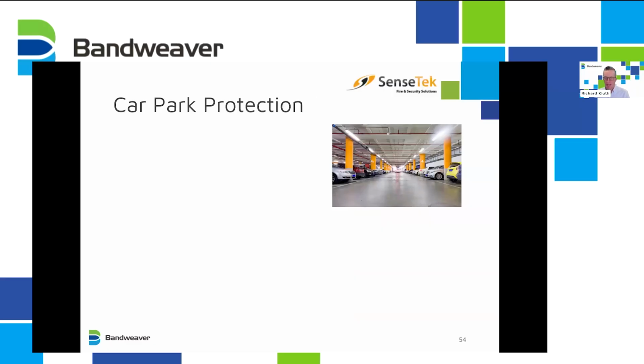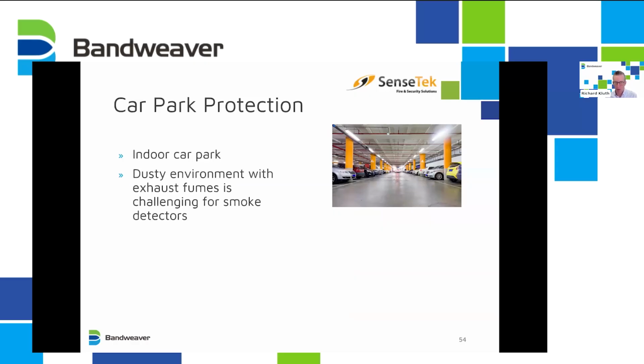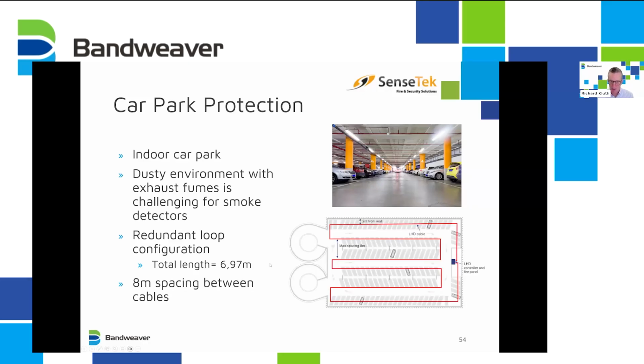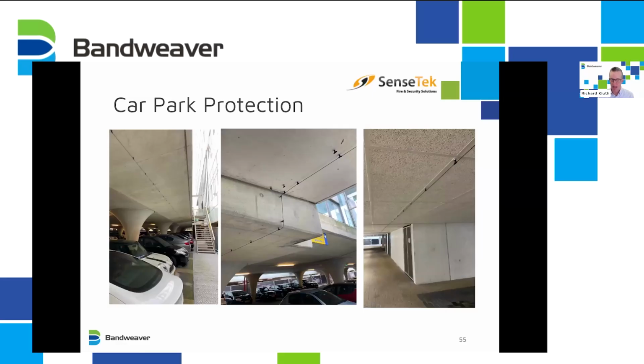So our final example is looking at car parks, and the reason for this is in the Netherlands they do car park commissioning tests that really demonstrate how sensitive this system can be. So if we look at this example, this is an indoor car park. They use heat detectors because it's challenging for smoke detectors. This is nearly 7 kilometers. They have 8-meter spacing between the cables. So when they do the commissioning test, they need to test the commissioning at 8 meters.